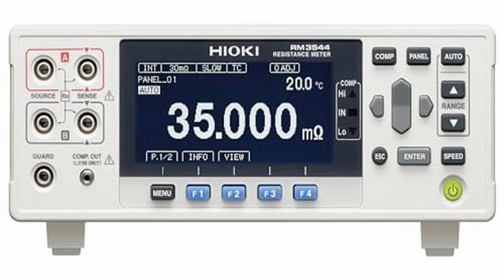One of the hidden strengths of the RM354401 is its external I/O capability. The instrument includes a connector that lets you hook up an optional LED comparator attachment. In a noisy workshop, you can set up the comparator to give you a clear visual cue. An LED will flash whenever the resistance crosses a threshold you define. I set mine to light up if a connector's resistance climbed above 5, which is handy when I'm doing quick continuity checks on wiring harnesses.